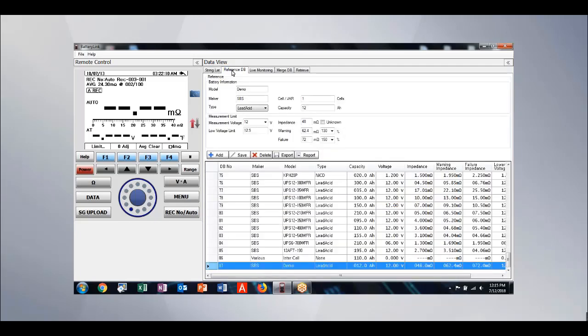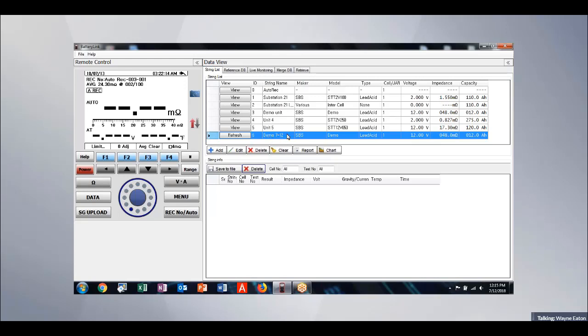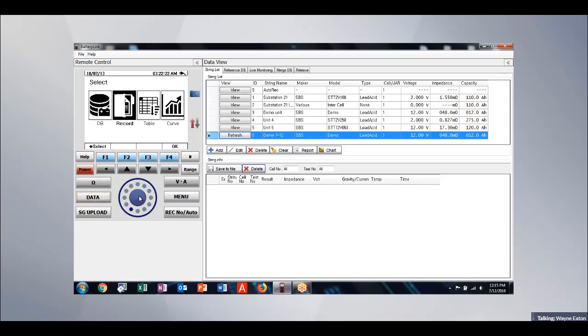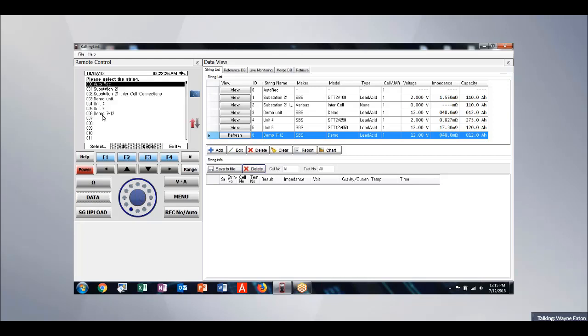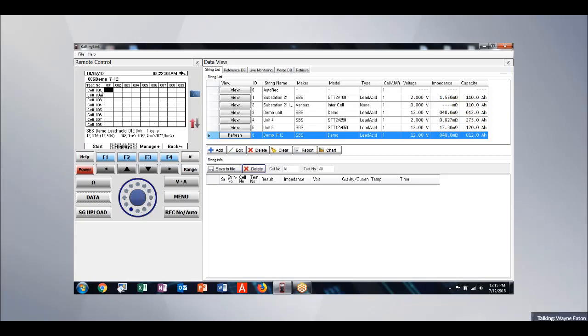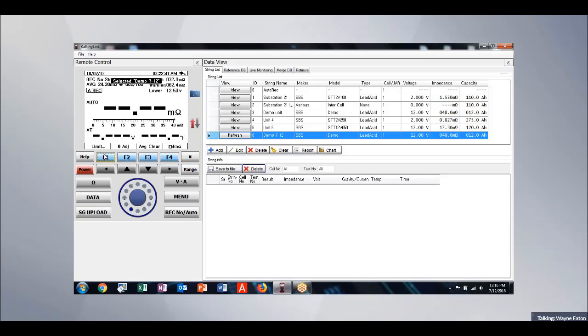So once I get my reference database set up and I get my string list set up, I would go out to substation demo 7-12. I'd press the data button. I'd go to record because I'm going to record new readings. I'm going to select that demo 712 from that list. I'm on test number 1, cell number 1, so I simply hit start. And the unit now comes up and it tells me that I'm on string number 6, test number 1, cell number 1. Here's my reference values that the readings are going to be compared to. And I'm ready to take my first measurement. So I just go out to the battery. The unit is an auto recording device, so I connect my positive and negative leads to that very first battery.